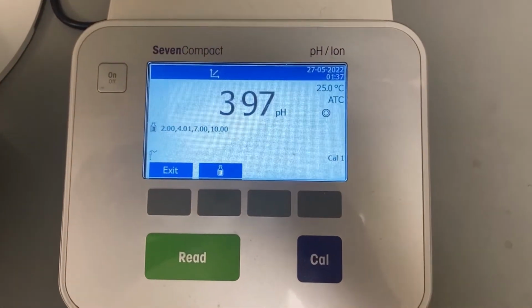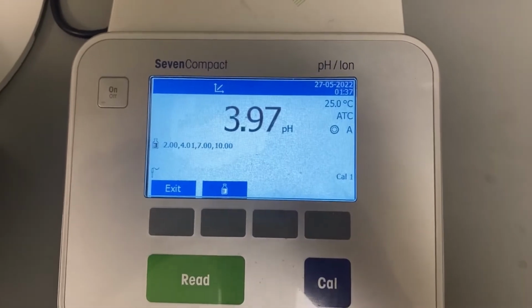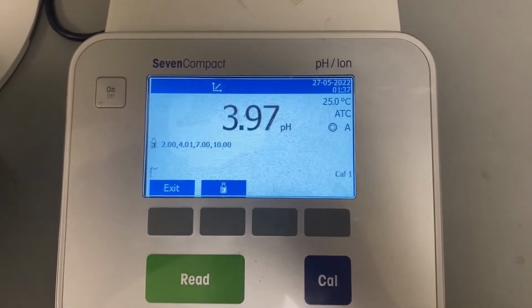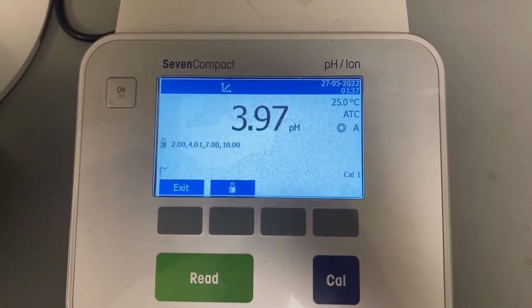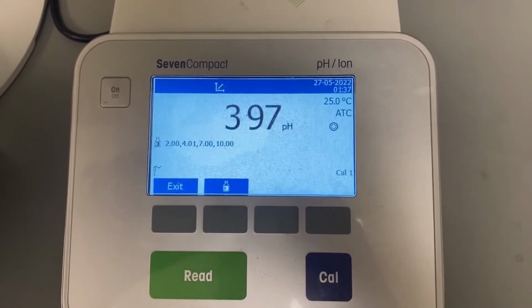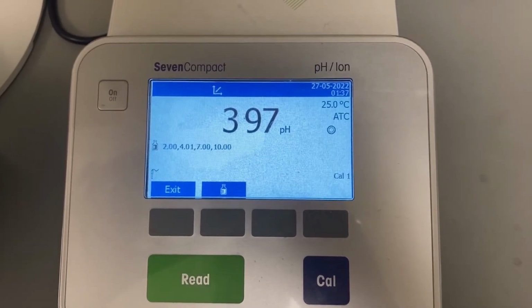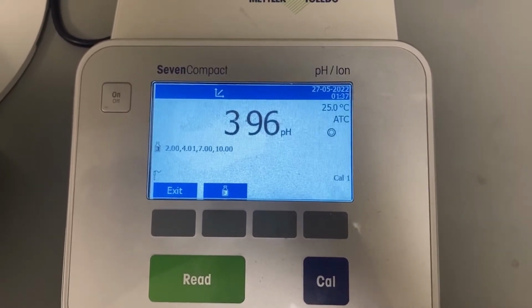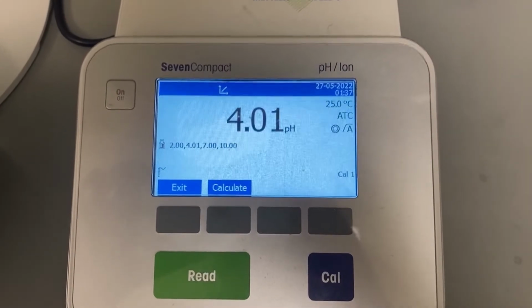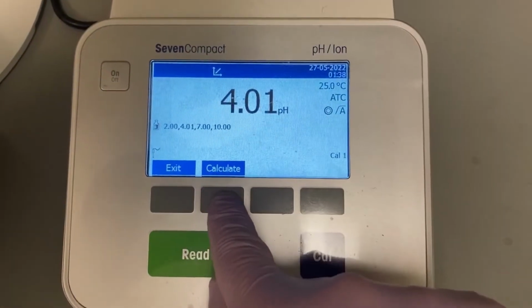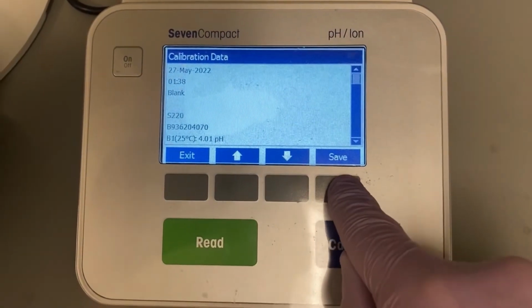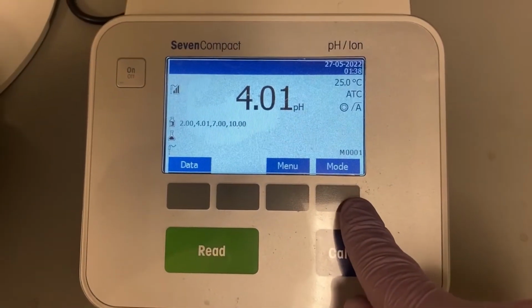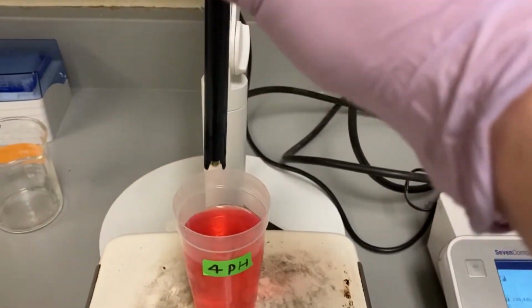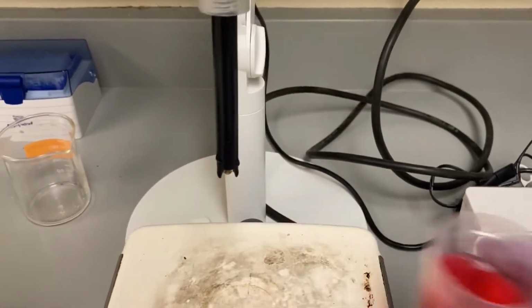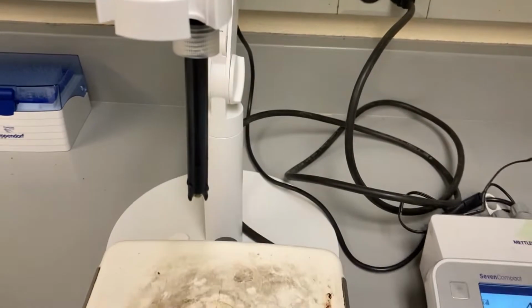Now we just wait for the pH meter to stabilize, and in this mode it will automatically detect the pH buffer we're using, in this case 4, and it will wait for the stabilization to happen, and then it will finish like that. When this happens, you hit calculate and then save, and then you can take the probe out and wash the probe.